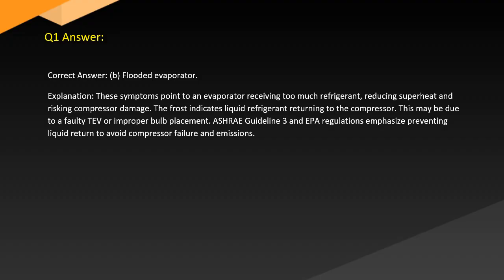Answer. Correct answer, B. Flooded evaporator. Explanation. These symptoms point to an evaporator receiving too much refrigerant, reducing superheat, and risking compressor damage. The frost indicates liquid refrigerant returning to the compressor. This may be due to a faulty TEV or improper bulb placement. ASHRAE Guideline 3 and EPA regulations emphasize preventing liquid return to avoid compressor failure and emissions.